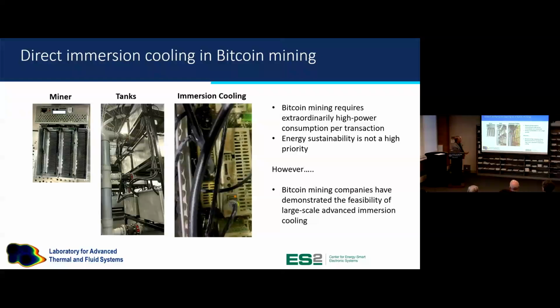They ventured into a place no conventional data center had ventured, trying out large-scale immersion cooling, where you take the electronics and put them directly into mineral oil or synthetic oil, cooling them by dropping the electronics into the oil itself. That's called immersion. Even though they're not sustainable, they taught mainstream companies that it's feasible to use immersion cooling on a large data center scale. It does work, though it has many problems associated with it, one being the compatibility between the materials of the electronics and the fluid itself.